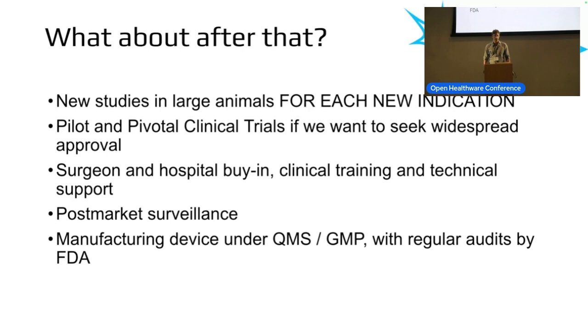The FDA also requires post-market surveillance, meaning that if anything goes wrong in a patient after the fact, you have to be constantly monitoring for this and then adjust those risk matrices in real time and make any design changes necessary to mitigate or ameliorate any new risks that might crop up. And then finally, you have to continue manufacturing these devices under a QMS, under GMP, and the FDA will regularly audit you and make sure that you're going through all the steps correctly and that there's nothing wrong with your system.